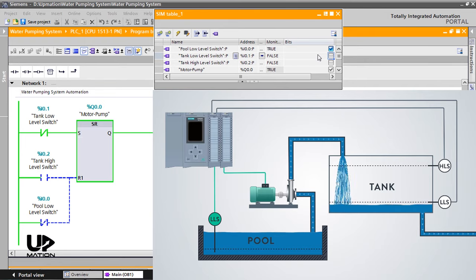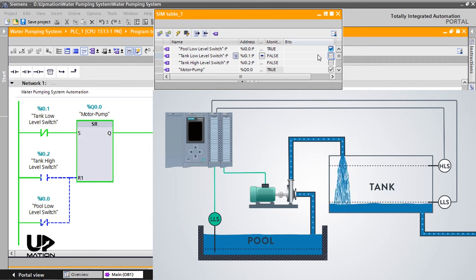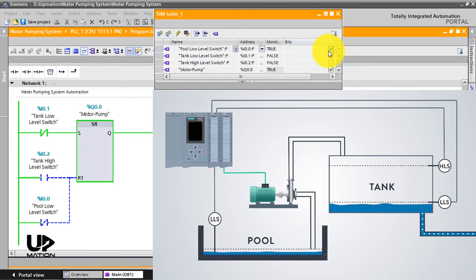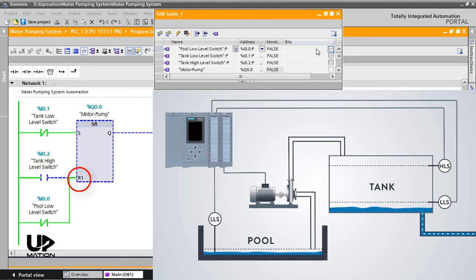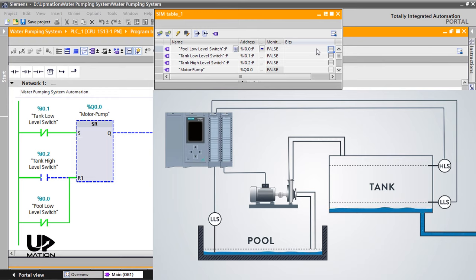This scenario will be continued unless the water level in the pool decreases and the low-level switch of the pool becomes inactive as a result. In this situation, the pump stops working instantly even if the set input of the flip-flop is active. This is due to the priority of the reset input in the SR flip-flop as we have talked about it in the previous video. And here is why we chose the SR flip-flop instead of RS flip-flop.